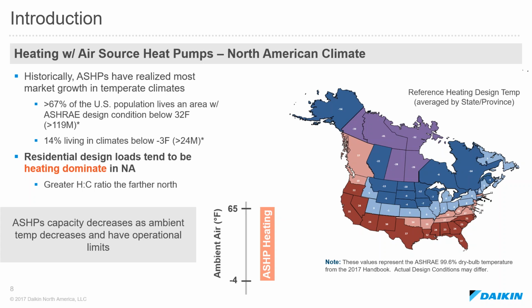And then in addition to that, residential applications tend to be heating dominant. That doesn't always mean you're heating more days out of the year than you're cooling, but it does mean that your heating load is larger than your cooling load. So now we're designing our systems for heating rather than cooling. So a lot of those traditional rules of thumb of maybe a BTU per square foot based off of an AC system, a system that only cooled, are no longer going to apply.